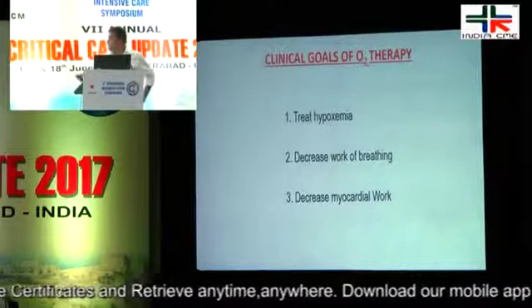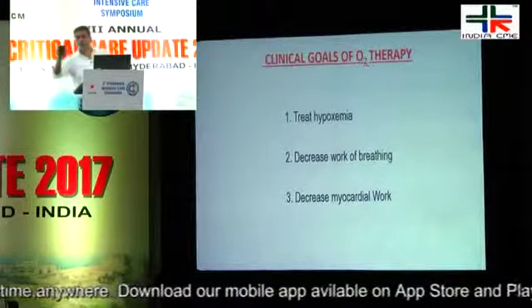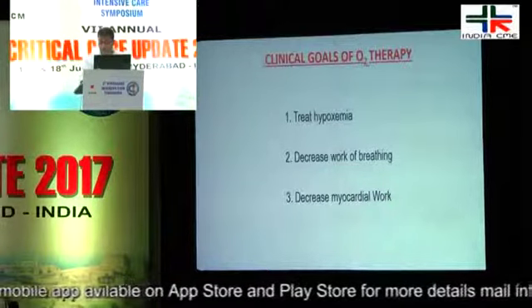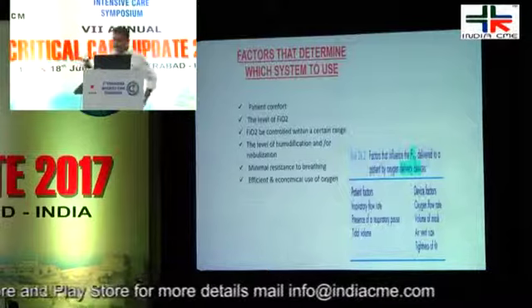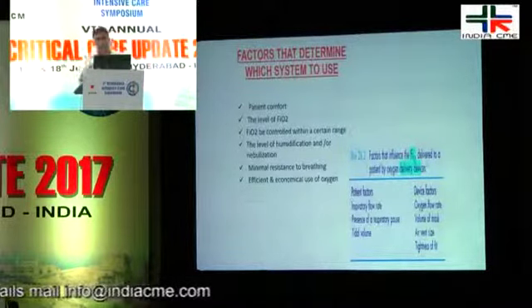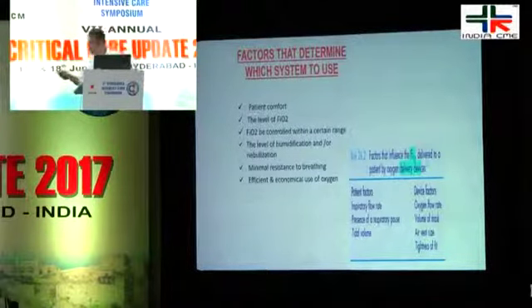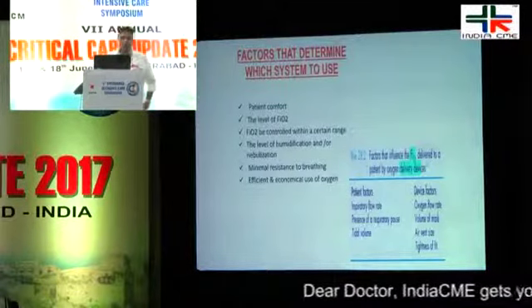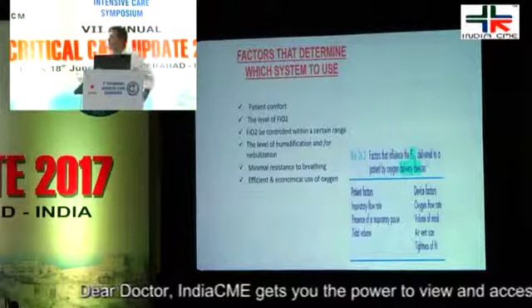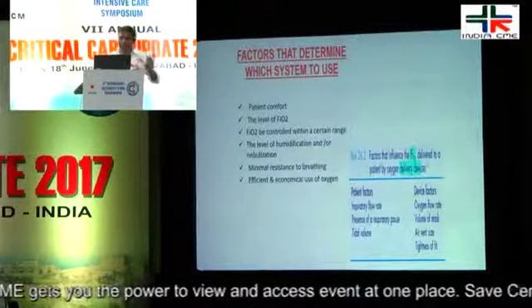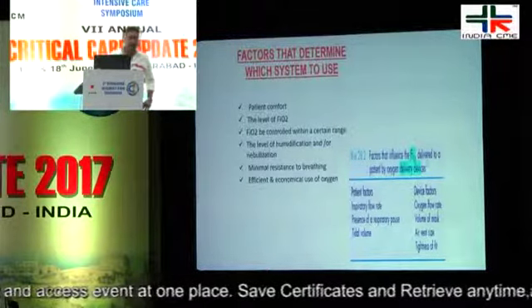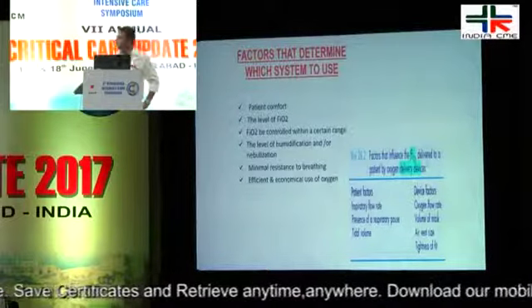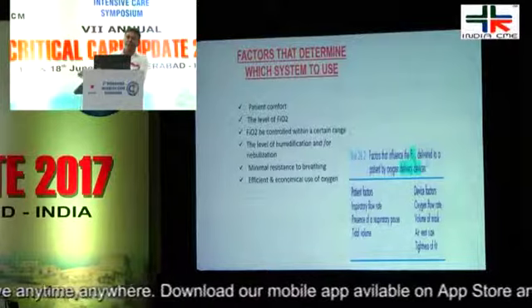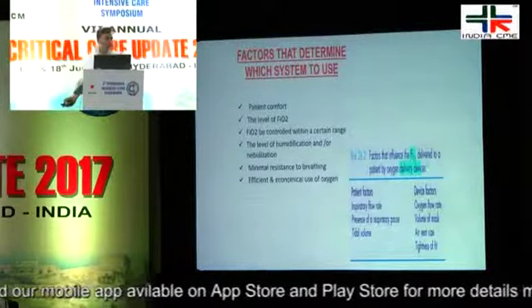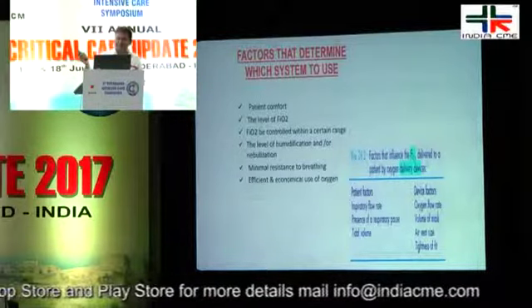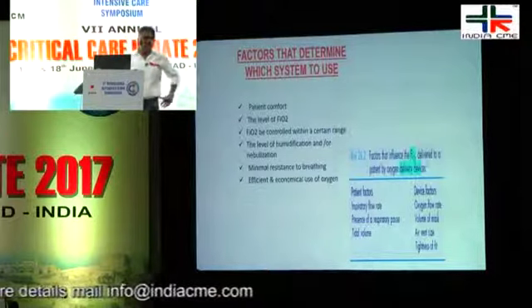You reduce the work of breathing, as well as the myocardial work, so you try to balance myocardial oxygen consumption and delivery. The factors that determine which system to use, whether non-invasive or invasive, apply to everyone. It depends on patient comfort, and the level of FiO2 required to correct the hypoxia, that means low levels or very high levels. FiO2 should be controlled within a certain range, that means predictable. It also depends on whether humidification or additional nebulization is required, and on the resistance to breathing; it is always good to have minimal resistance. Efficiency and economy of using oxygen matter too, because nowadays are we charging for the oxygen here in Hyderabad? Yes, definitely. So you have to be efficient and economic in using it.